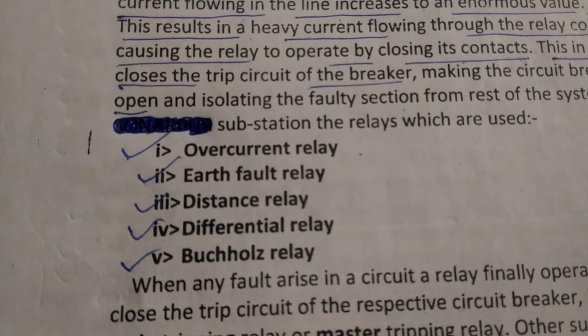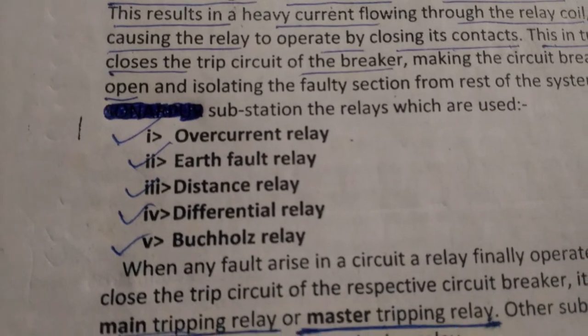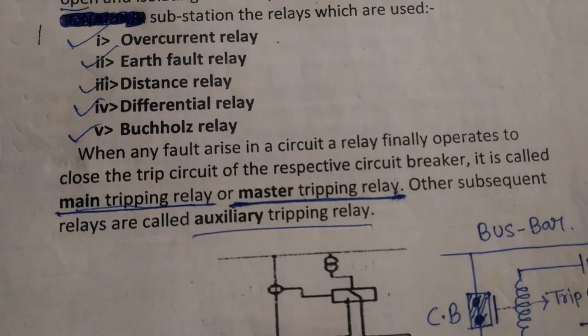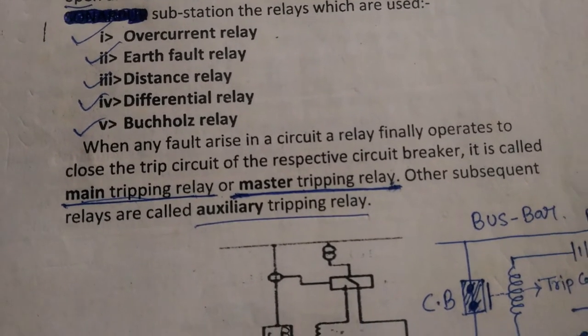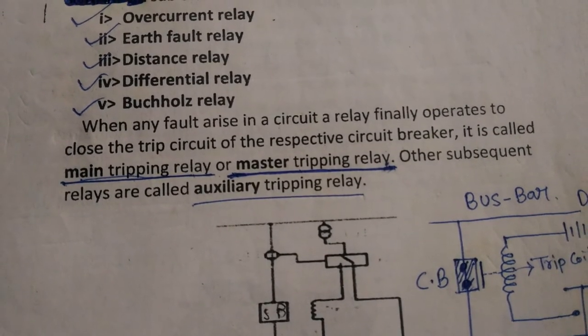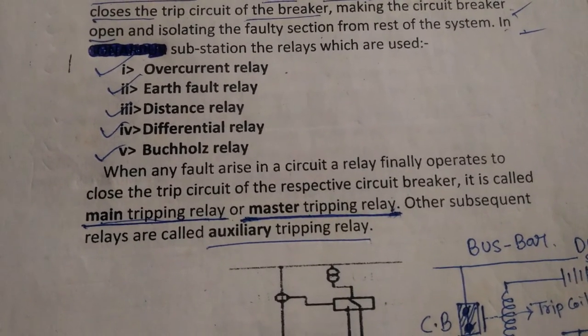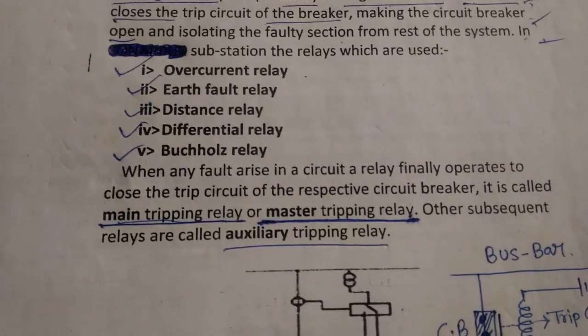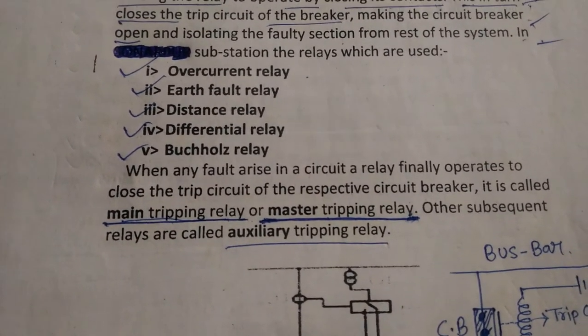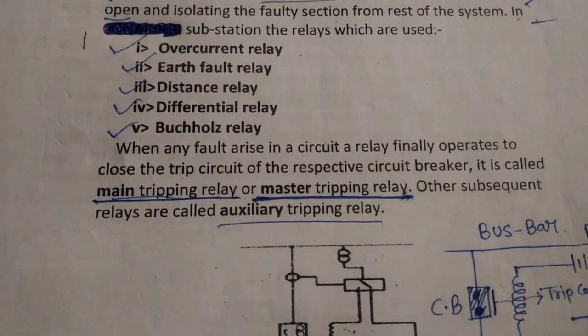The Buchholz relay is used on transformers, and the auxiliary relay coil is attached to the back side of the panel. When any fault arises in the circuit, the relay operates to close the trip circuit of the circuit breaker — this is called the main tripping relay or master tripping relay. Other subsequent relays are called auxiliary tripping relays. The master trip relay is the 86 relay, and it is parallelly connected with all other relays: overcurrent, earth fault, distance protection, differential protection, OTI, WTI, alarm trip, PRV, OSR trip — everything is connected to the 86 relay.